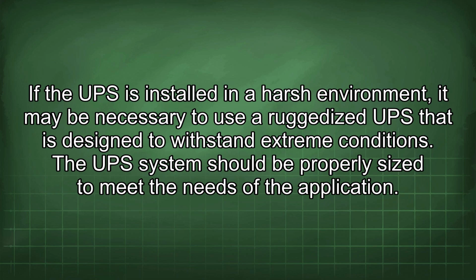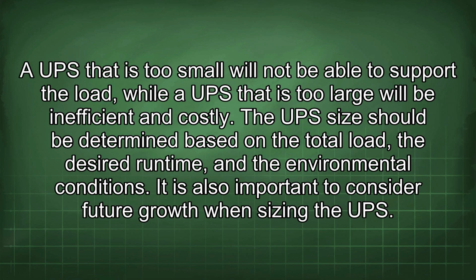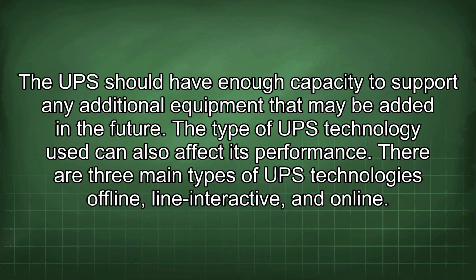The UPS system should be properly sized to meet the needs of the application. A UPS that is too small will not be able to support the load, while a UPS that is too large will be inefficient and costly. The UPS size should be determined based on the total load, the desired runtime, and the environmental conditions. It is also important to consider future growth when sizing the UPS. The UPS should have enough capacity to support any additional equipment that may be added in the future.